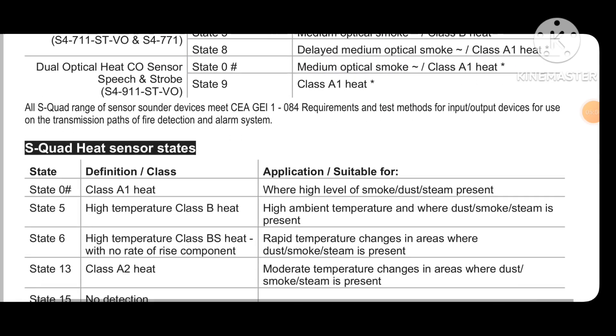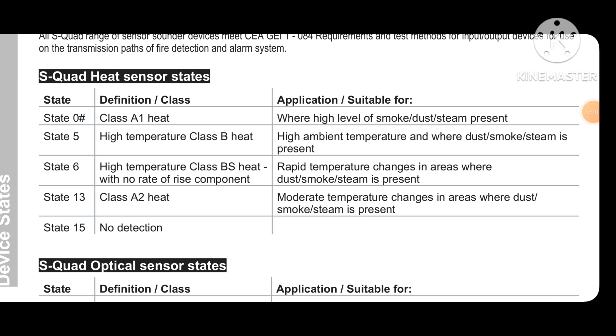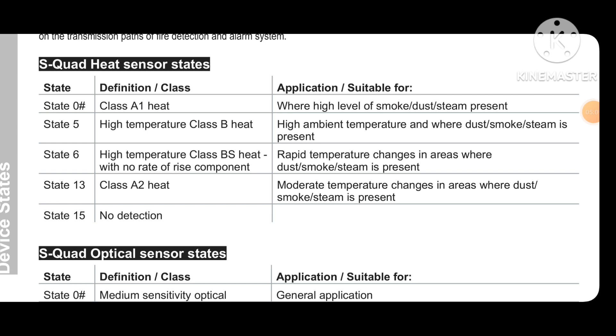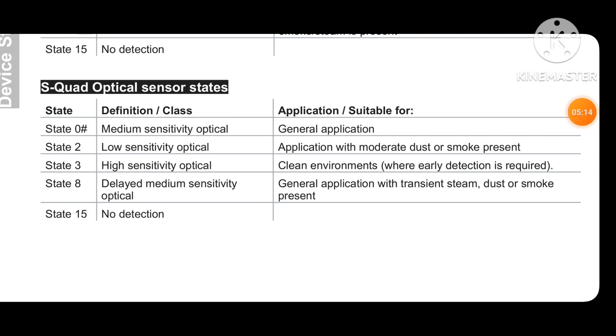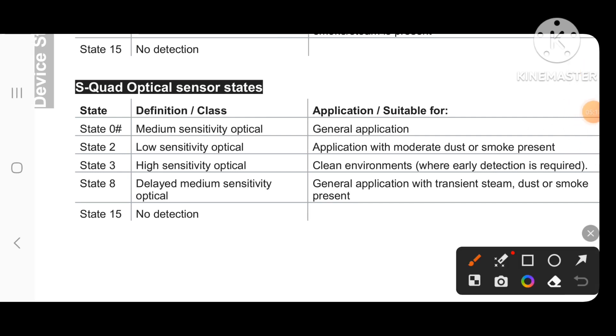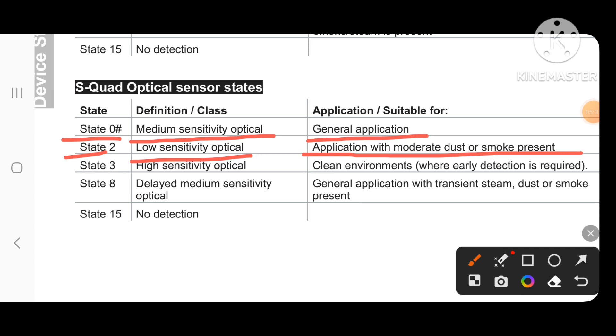For scored heat sensor states: state 0 to state 15 no detection; state 5 is high temperature class B heat. For optical sensors: state 0 is medium sensitivity for general applications; state 2 is lower sensitivity optical, for operation with moderate dust or smoke present; state 3 is high sensitivity optical for clean environments where early detection is required. State 8 is delay medium sensitivity, suitable where transient steam, dust, or smoke may be present.